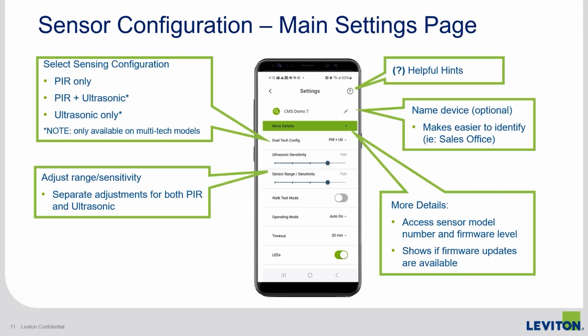Once you have connected to a sensor, you'll be brought to the main settings page. Here you can rename the device, which we highly recommend doing. This helps keep track of which sensors have already been programmed. Under More Details, you can review the sensor model number and firmware level and check if there are any firmware updates available. For multi-tech models that include both PIR and ultrasonic, you can disable one of the sensing technologies if desired and increase or decrease the sensor range by adjusting the slider up or down.